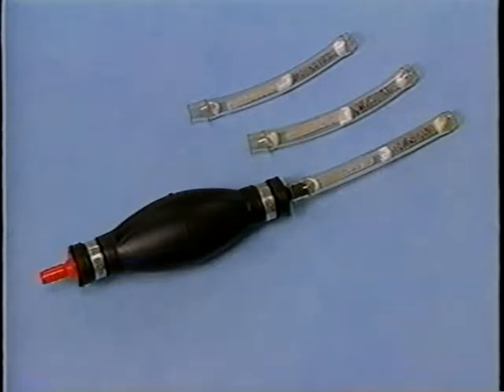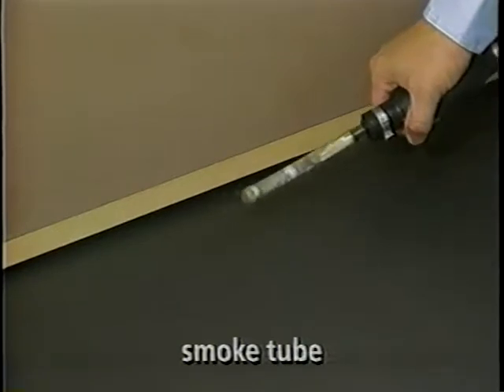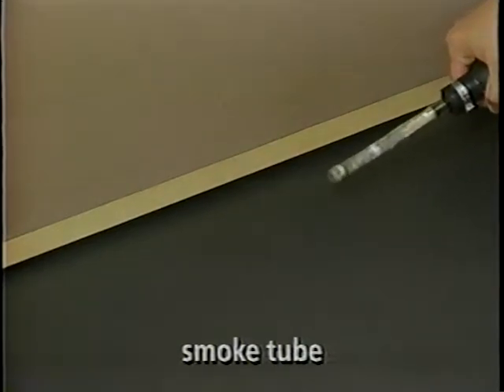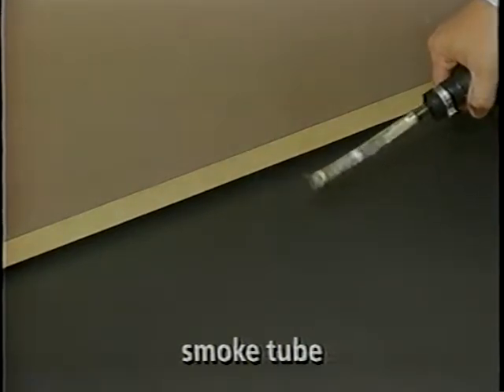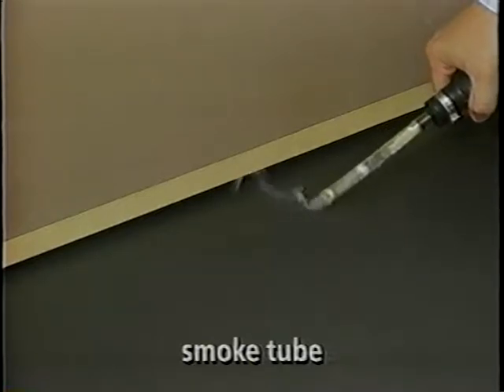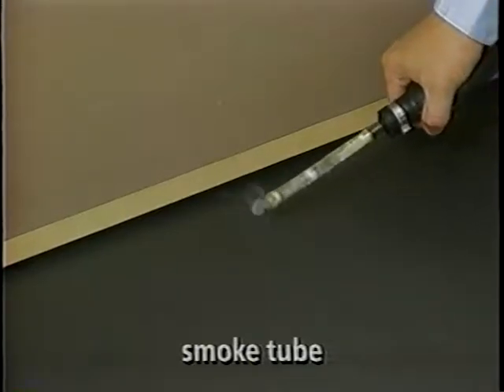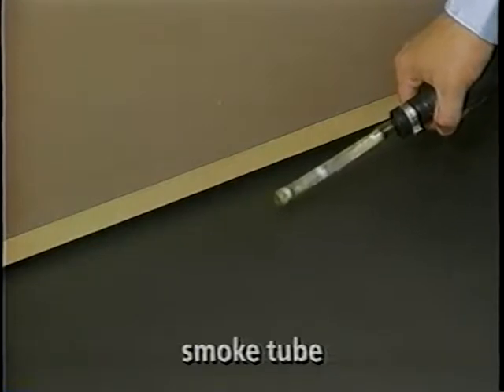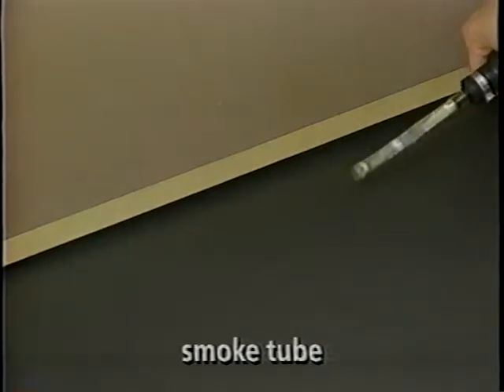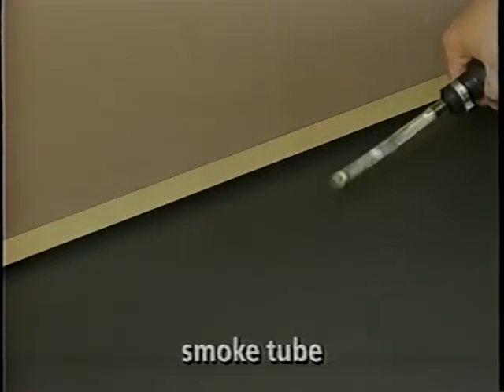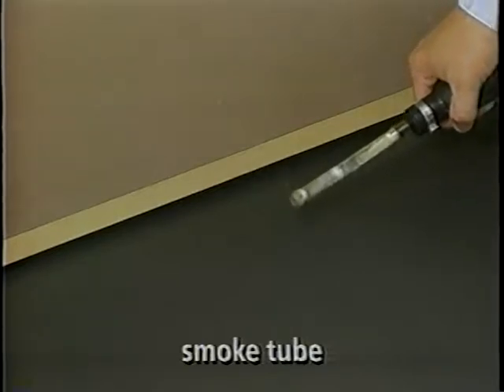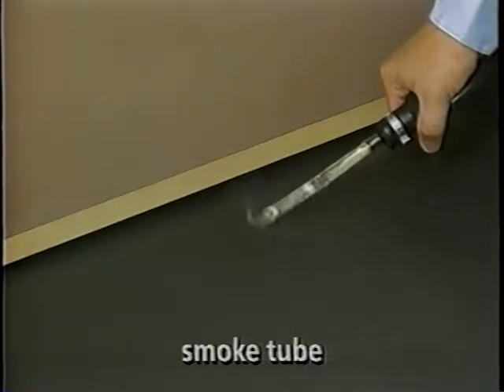You can buy smoke tubes such as these from safety supply companies. Slowly release the smoke in the hallway at a point about 2 inches out from the center of the door. Aim the smoke in a direction parallel to the room door. If the room is at negative pressure, the smoke will be seen to go under the door and into the room. The test should be repeated at least once or until the results are consistent.